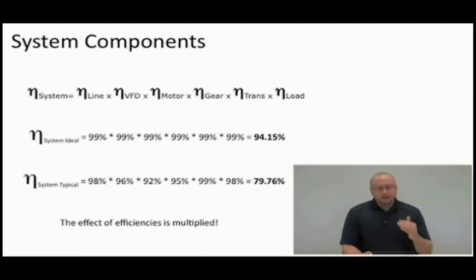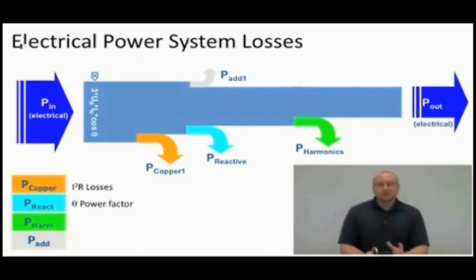So now we're going to talk about each component. We're going to start with the electrical power system that's going into the inverter. The electrical system that feeds the inverter, or the motor if you don't have an inverter, is going to have some losses. You're going to have copper losses, some reactive power losses, some harmonic losses. The main loss that we're going to concentrate on is reactive power, because that's something we can actually do something about to help minimize those losses. But the main loss in the electrical power system is the copper losses.